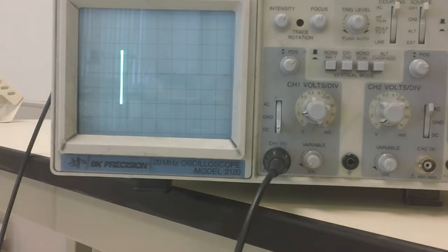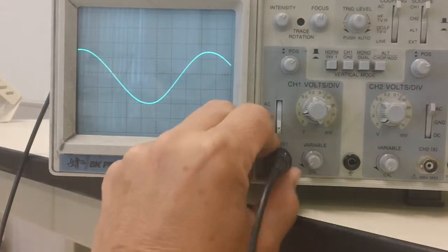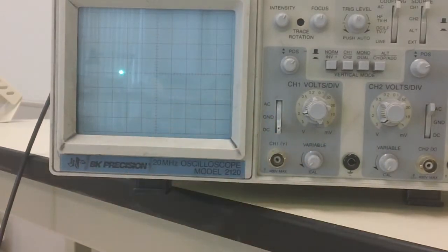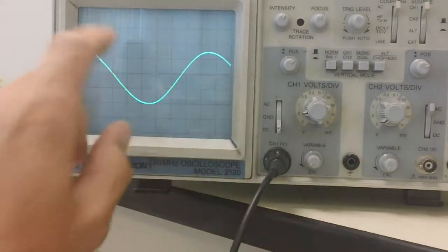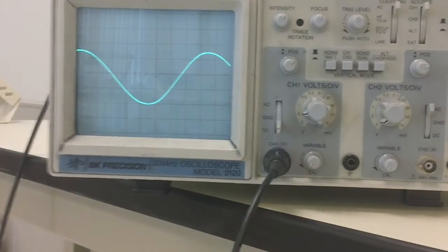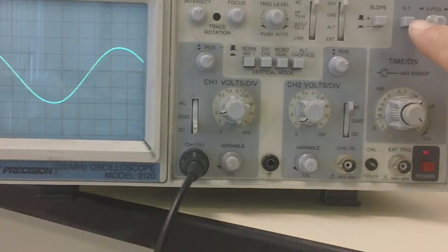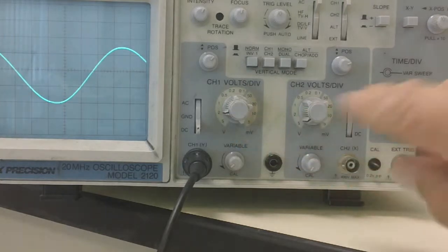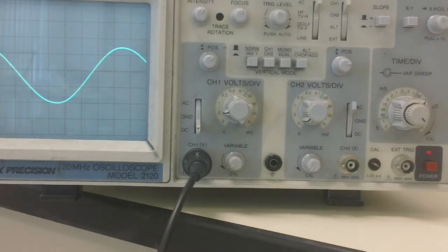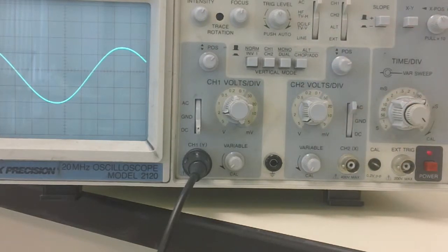But always remember to take that back out, because if you take this input off of here and you have the XY pushed, you end up with a dot and you will burn a hole or a spot in the screen on your display. So make sure that you watch that very carefully. And when you push the XY, channel 2 will give you the horizontal voltage, or the voltage in channel 2 horizontally is a better way to put it.